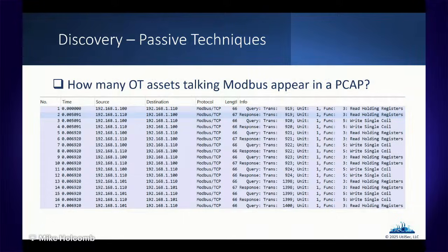And you can read data from memory of the PLC, but you can also override, or write to those sections or data points in memory to then make changes to what's going on in the actual real world. And that's why unencrypted and unauthenticated protocols like Modbus are dangerous, because they allow somebody to connect to the asset, not only read what's going on in memory, but also make changes to the data in memory, which can be reflected in the real world.